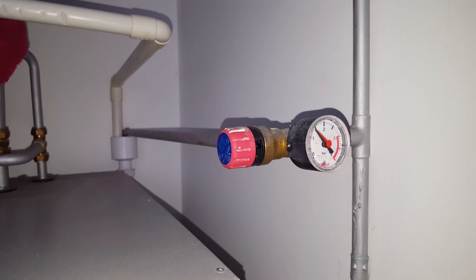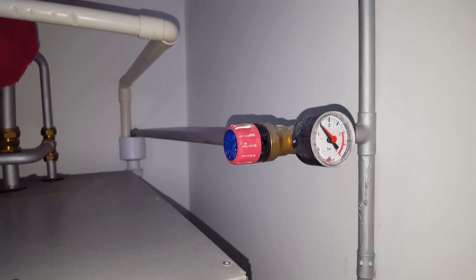The temperature is climbing up now — it was on 56°C when we first came to this unit, and the pressure was down on zero. It's now been topped up to the right pressure and everything is now working properly, so the temperature is going up slowly and will eventually get over the 60°C mark.